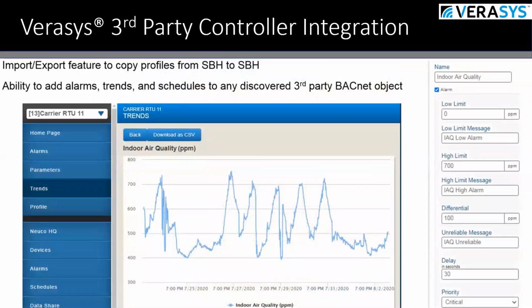Once you have those points, you can create the profile and copy it from one Smart Building Hub to another, or even add alarms. You can add trends, set high and low limits on alarms, set schedules, and do all the things you could do with any other controllers, once you've selected and created that profile for the points you want to use on those third-party BACnet objects.